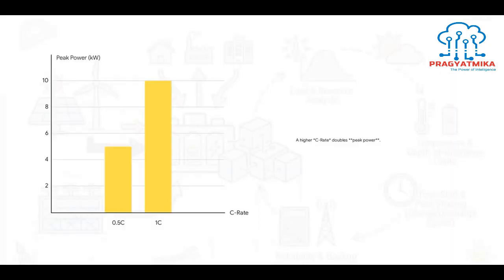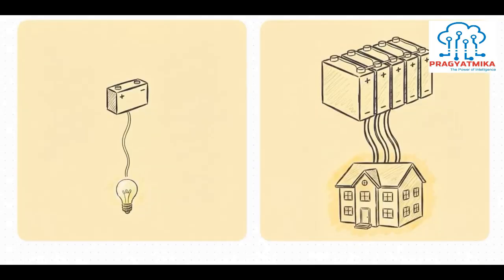Let's put this into perspective. A 10 kilowatt hour battery rated at 0.5 C is only going to deliver 5 kilowatts of peak power. But at 1 C, that exact same battery delivers 10 kilowatts. We are talking about the exact same physical footprint, the exact same amount of stored energy, but literally double the instantaneous output capabilities. This proves once and for all that identical energy does not mean identical power. A 0.5 C setup is fine for basic backup like lights and refrigeration, but you need 1 C to handle those heavy surges, your AC units, your EV chargers, without the system totally faulting out.